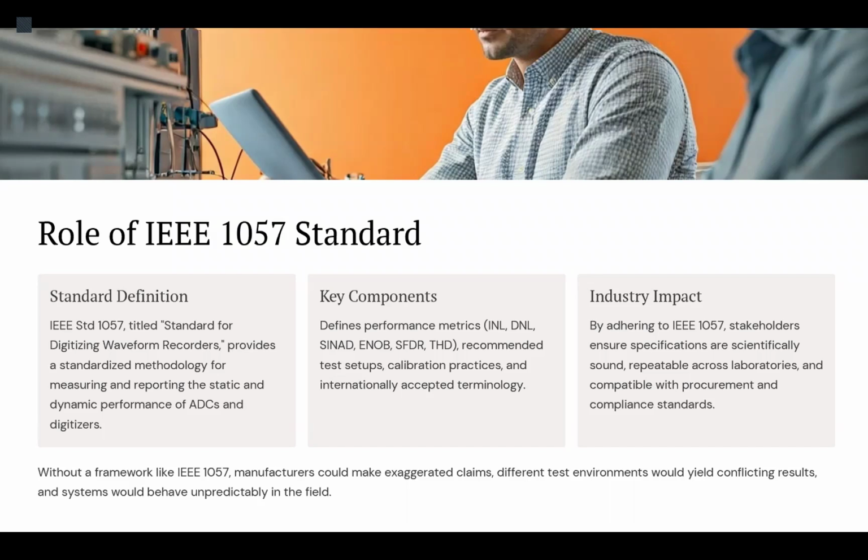So we define parameters like INL, DNL, THD, and we set some protocols for testing the ADC. These standards recommend how we could have a test setup configuration, how we have to apply calibration, and how we have to document the result.